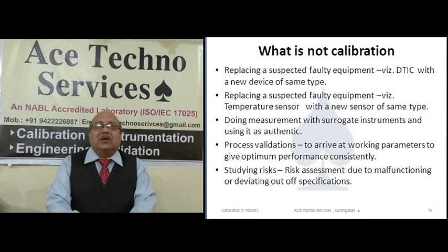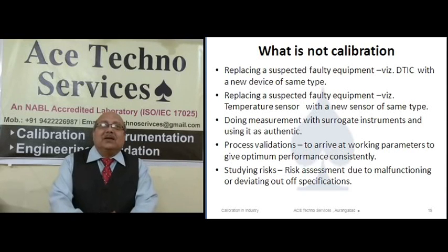Here I am going to talk about what is not calibration. My reference is always the case study. Replacing suspected faulty equipment, for example, the DTIC with a new device is not a calibration.